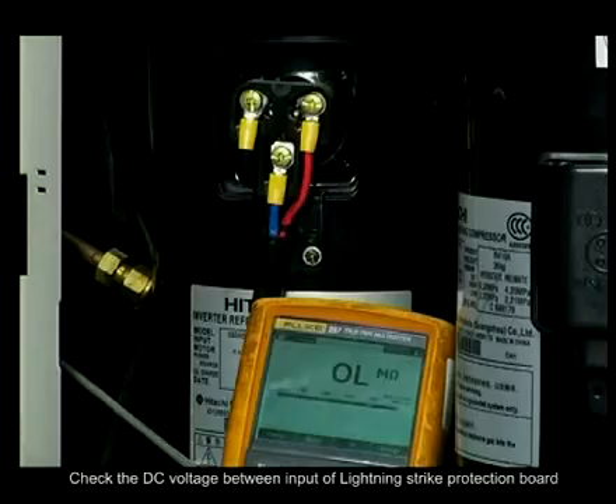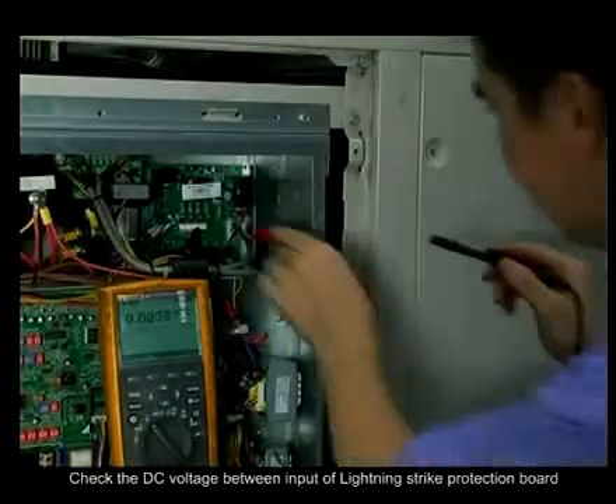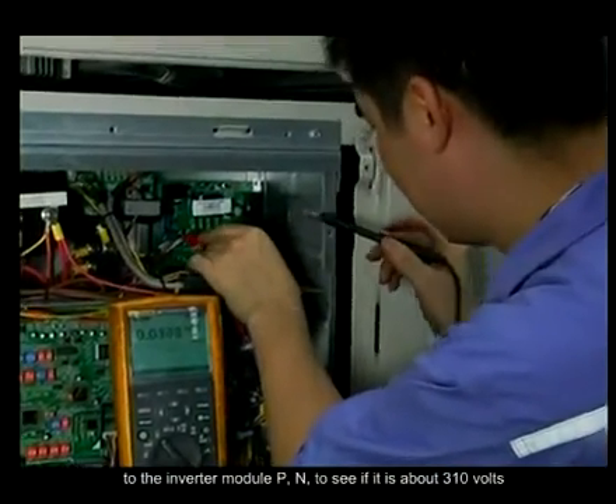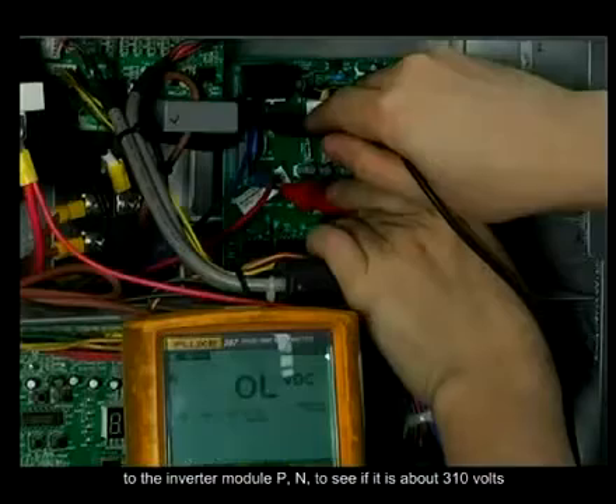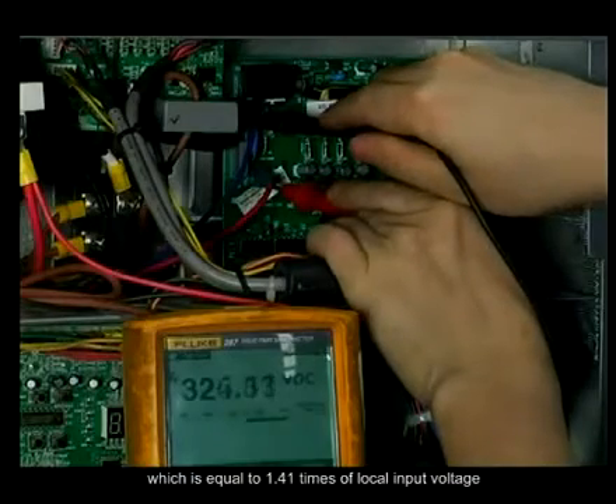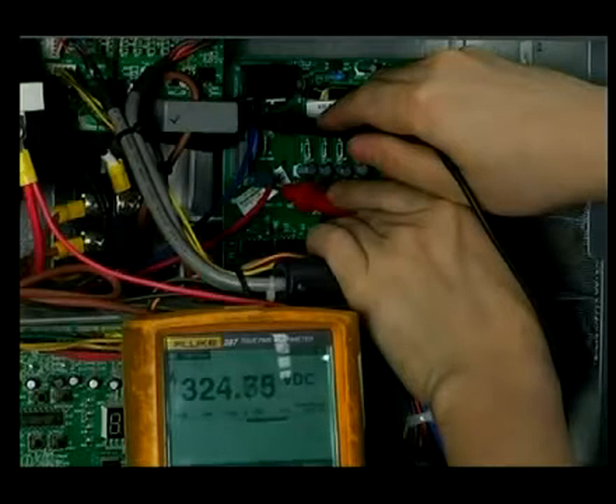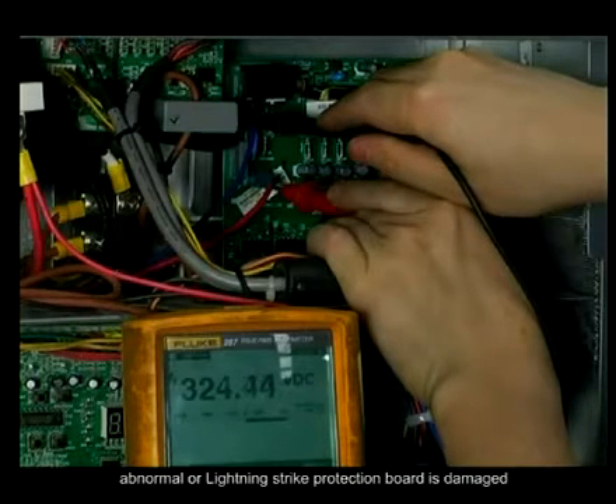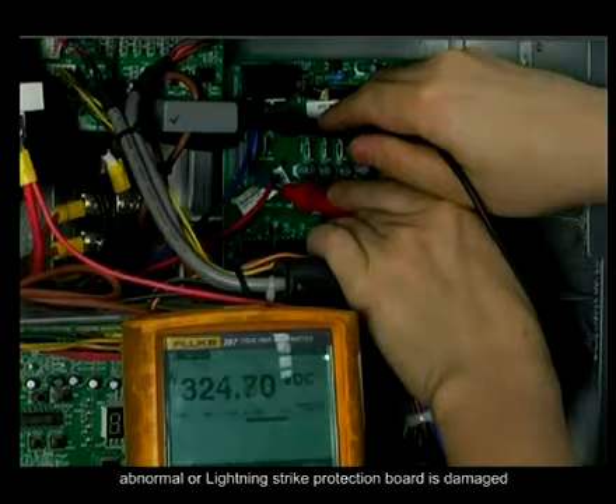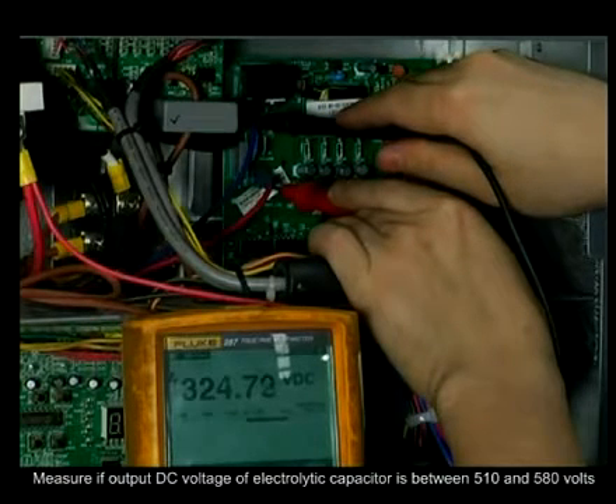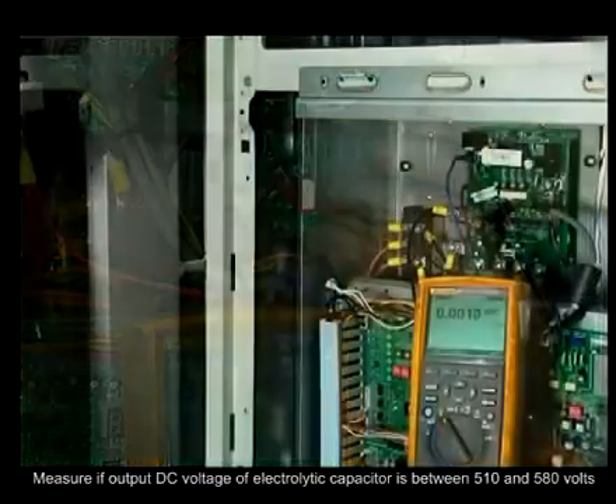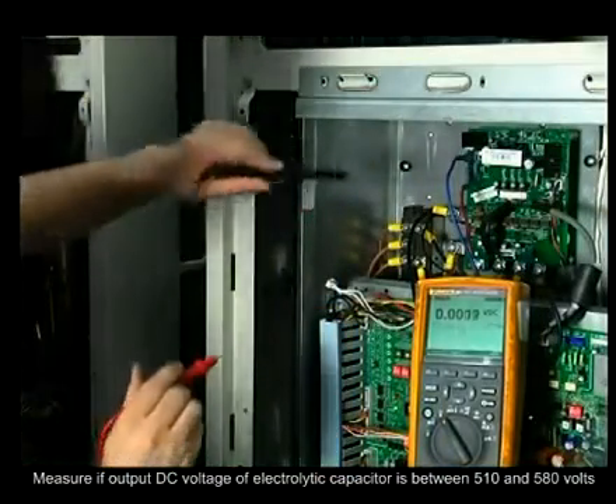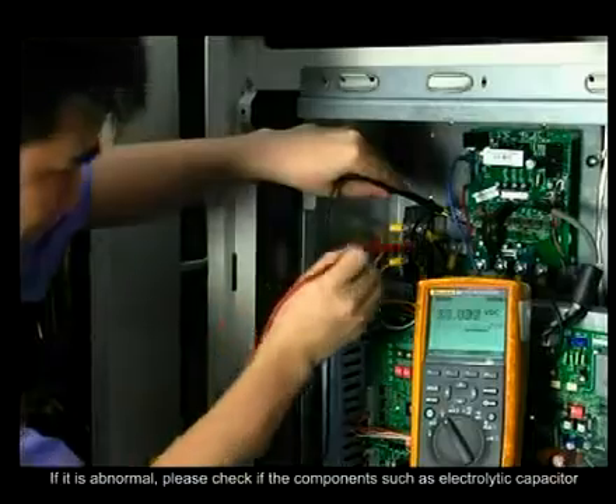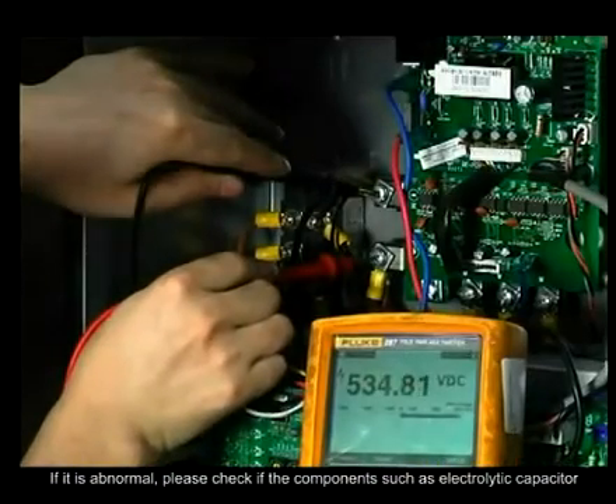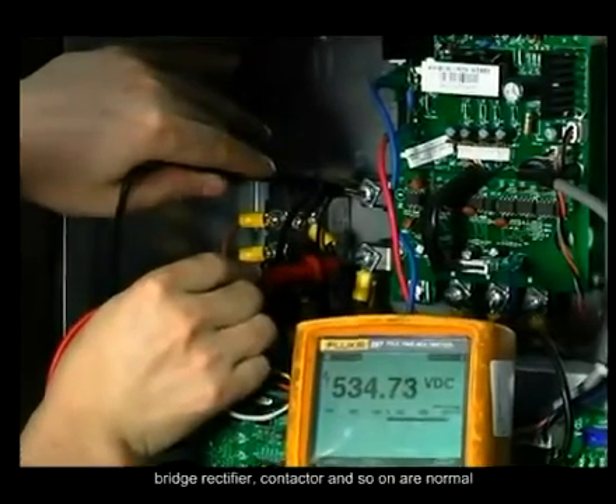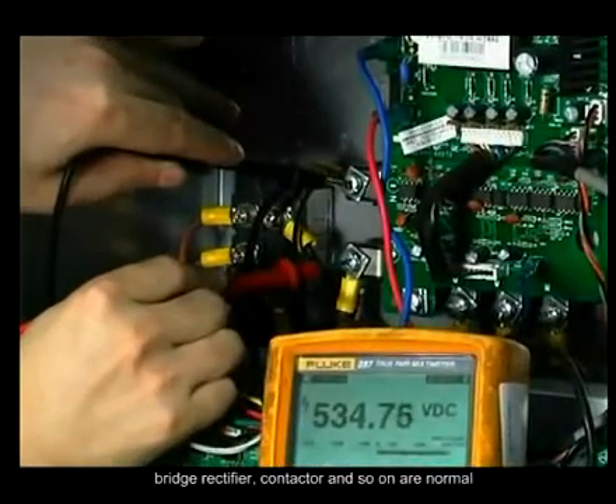Check the DC voltage between the input of the lightning strike protection board and the inverter module PN to see if it is about 310 volts, which is equal to 1.41 times the local input voltage. If it is abnormal, the voltage of the power supply is abnormal or the lightning strike protection board is damaged. Measure if the output DC voltage of the electrolytic capacitor is between 510 and 580 volts. If it is abnormal, please check if the components such as the electrolytic capacitor, bridge rectifier, contactor, and so on are normal.